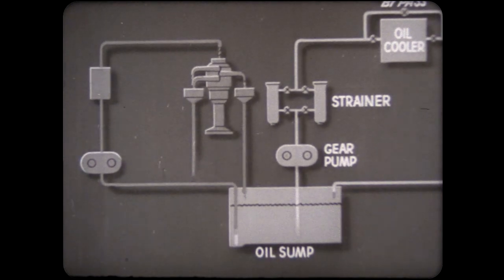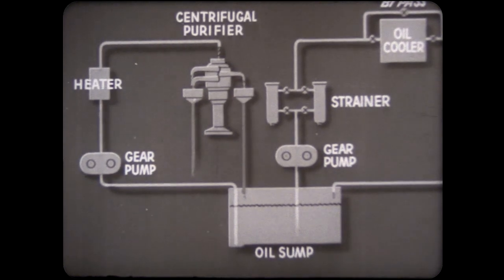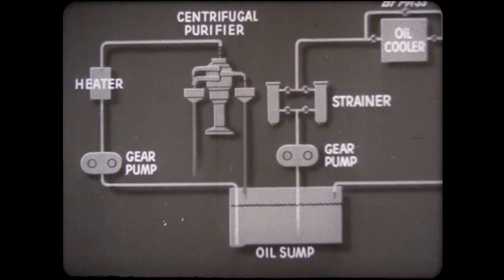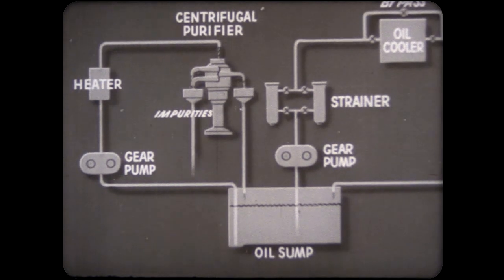In this process, the oil is pumped from the sump tank, and after being thinned by heating, it is carried to a centrifuge. Here, water and any remaining solid impurities are whirled out by centrifugal force, and the purified oil is returned to the sump tank.